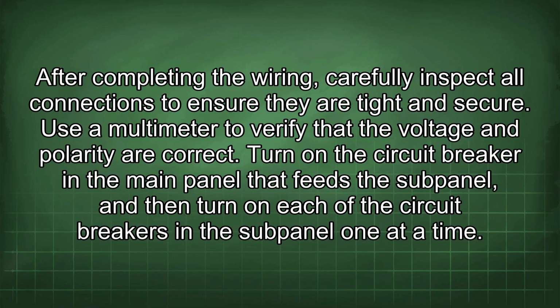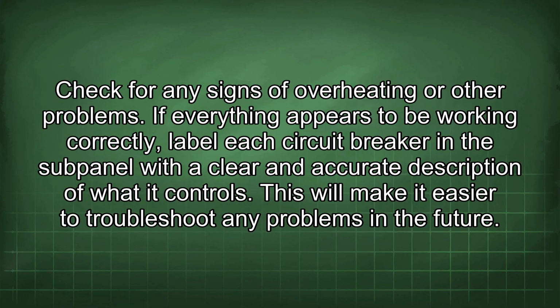After completing the wiring, carefully inspect all connections to ensure they are tight and secure. Use a multimeter to verify that the voltage and polarity are correct. Turn on the circuit breaker in the main panel that feeds the subpanel, and then turn on each of the circuit breakers in the subpanel one at a time. Check for any signs of overheating or other problems.